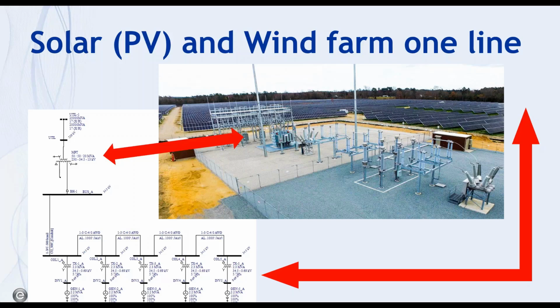From the grid interconnection perspective, the rule of thumb is that only the equipment that can be seen by or interact with the AC power grid is required to be modeled in the BES studies. So that's just a rule of thumb. With that rule of thumb, you can see that I didn't model my inverter as a solar panel and inverter as we usually do in EasyPower. Instead, I only use a generator to model the inverter, and I may not care too much about what's beyond my inverter. It can be a solar panel, it can be a Type 4 wind turbine, it can even be an energy storage, because I only care about how the inverter behaves, how the inverter interacts with my grid, right? So I can use a generator to represent it.